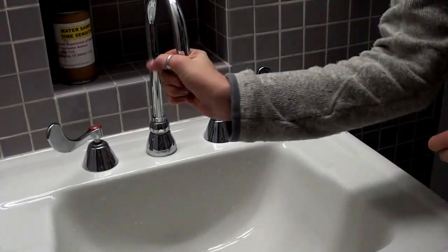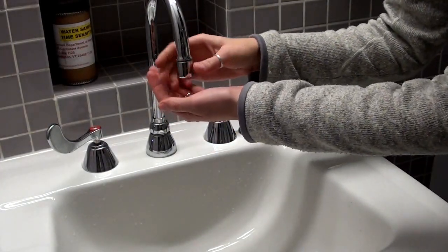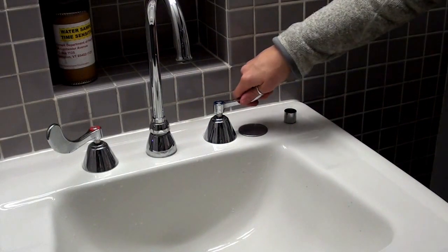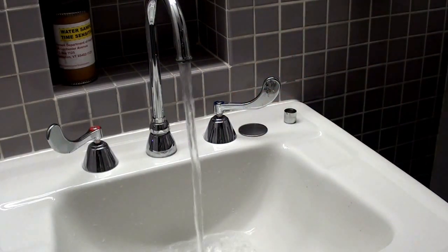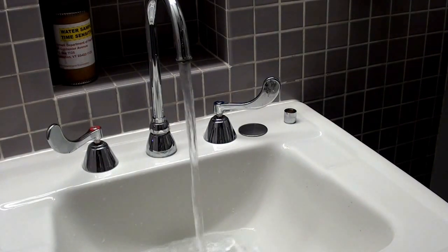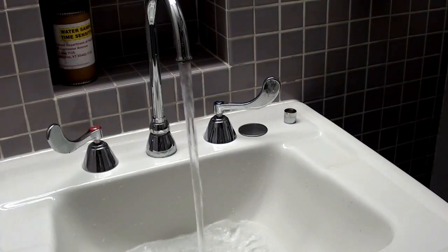The assessment requires that operators review their sampling locations and sampling protocol. Section 2 of the form goes through sampling sites and sampling protocol and the potential they have on the results. It is really important to try to use the best sample taps at the best locations in order to evaluate the system's integrity.